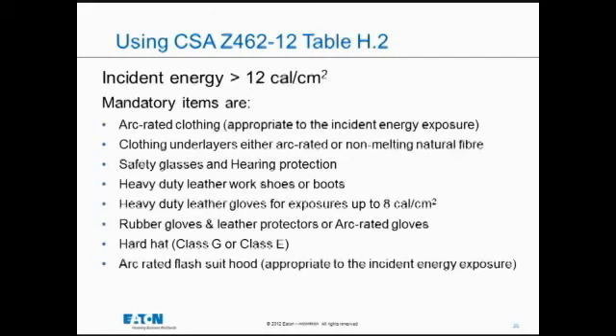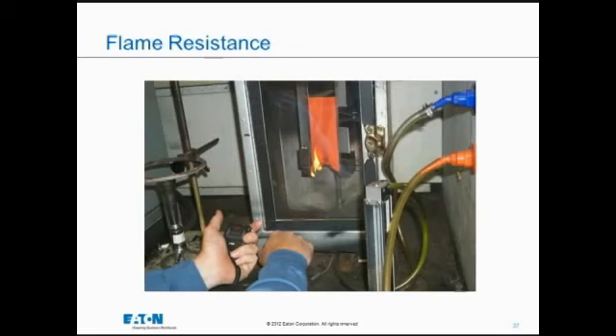To get arc-rated material, we first find out if it's flame-resistant material, and there's a test to prove whether it's flame-resistant. That's shown in this picture here. The material is lit on fire. It's then checked with a stopwatch to see how long it takes for it to snuff out the flame, and then they measure the char length, or how much disappeared, and if it passes certain criteria, it becomes a flame-resistant material. That's certainly fine for race car drivers, people that are putting out fires, firefighters, people that work in petrochemical plants where there's a fire hazard from fuel. But we want to take it to the next level.